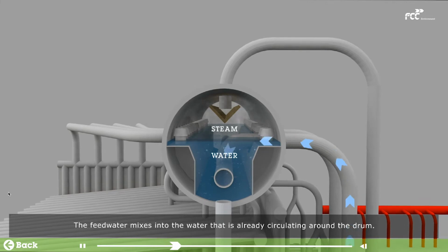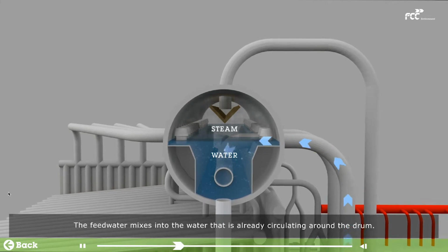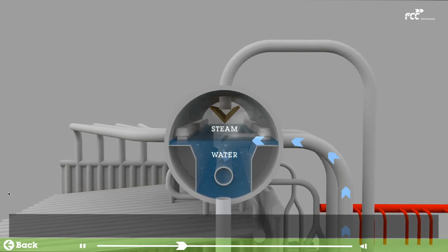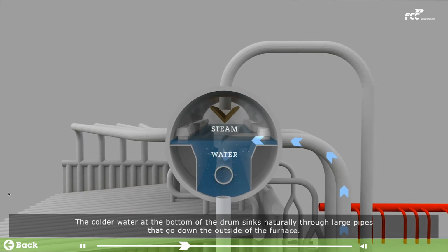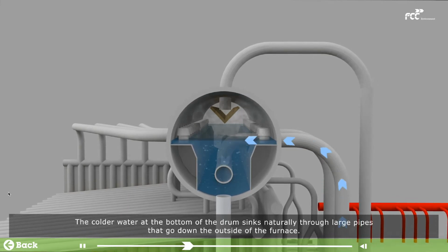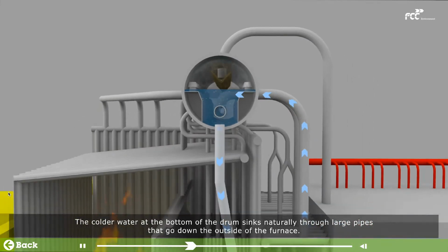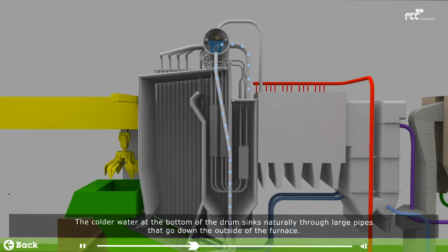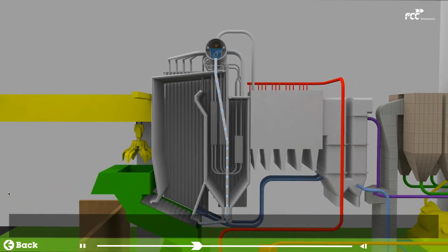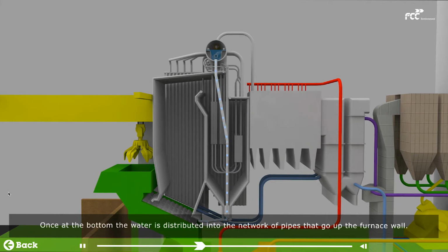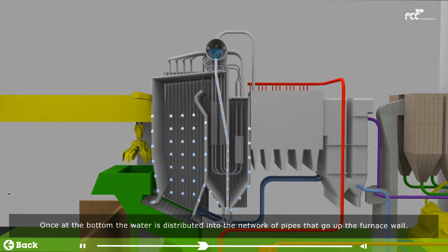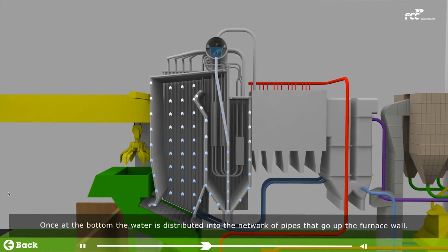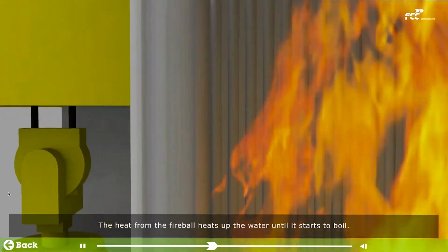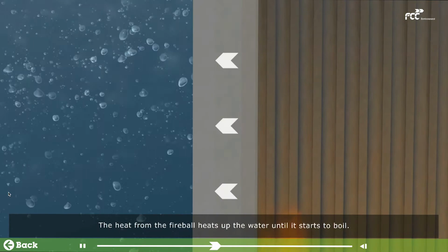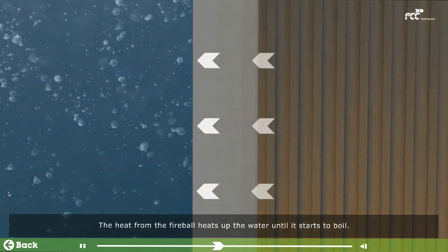The feed water mixes into the water that is already circulating around the drum. The colder water at the bottom of the drum sinks naturally through large pipes that go down the outside of the furnace. Once at the bottom, the water is distributed into the network of pipes that go up the furnace wall. The heat from the fireball heats up the water until it starts to boil.